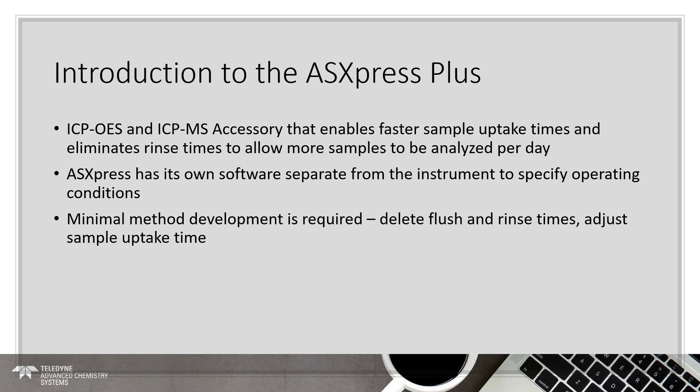What this is is an accessory for ICP optical and ICP-MS systems that enables faster sample uptake times and eliminates the rinse time to allow more samples to be analyzed each day or each shift. The ASXpress Plus has its own standalone, very small, light software, which is separate from the instrument that specifies its operating conditions. And typically, the method development time to get this installed and running is fairly minimal. What we normally ask is that you'd have your standard operating parameters. We want to walk into the lab and know that you're already getting quality data. And then with the ASXpress Plus, we can simply speed up your analysis time while we maintain the quality of data already in place.